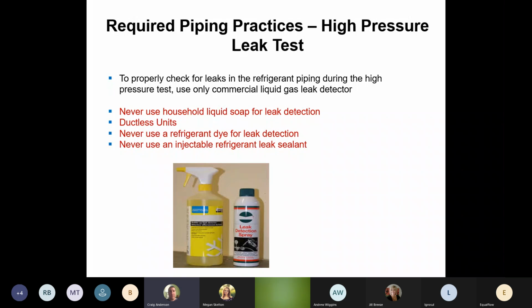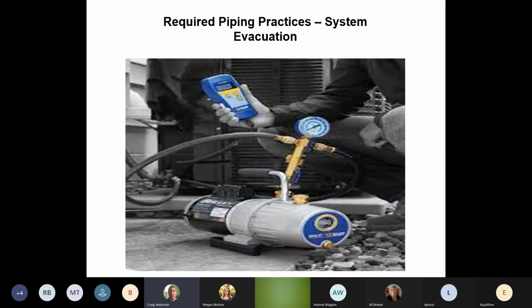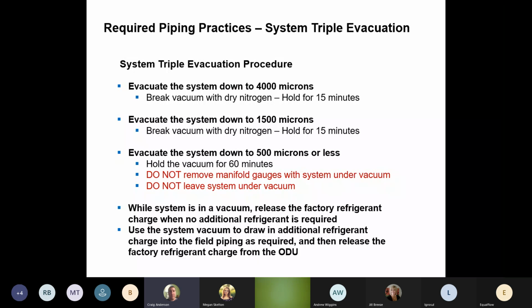So vacuum, that's a big one. We were talking about that before. Let's start off the beginning of the season. If your vacuum pumps have been sitting in your truck and you're not using them, get them in the shop, change the oil, check all your seals on it. We want to make sure we get a proper evacuation. If we don't, we're going to get contamination and moisture in the system, and it's just going to cause havoc on the compressor later on down the road, or it's going to cause havoc all year round on that air conditioner. So let's do a proper evacuation. It's called a triple evacuation procedure. It's been in the manual for years. This is not something new. Let's turn the vacuum on.